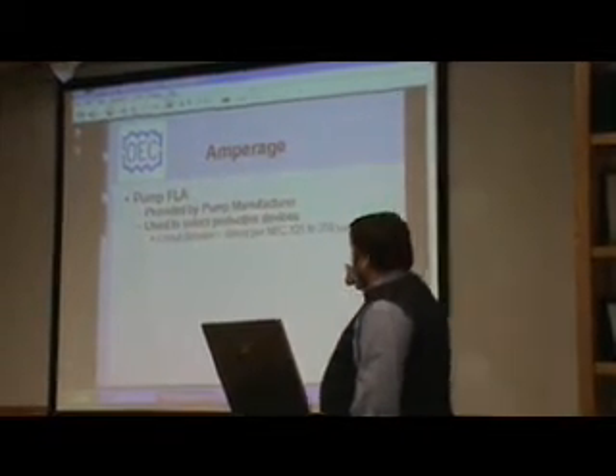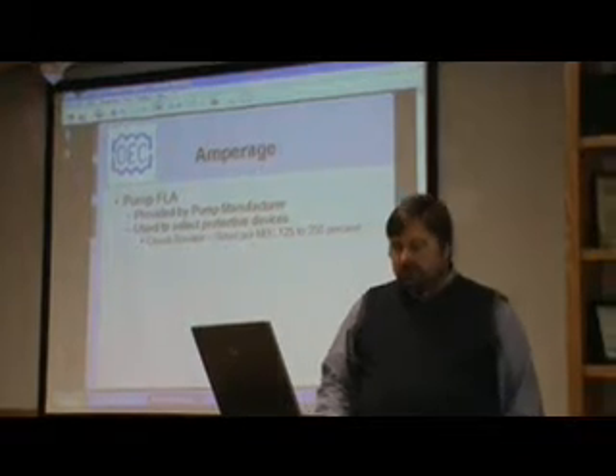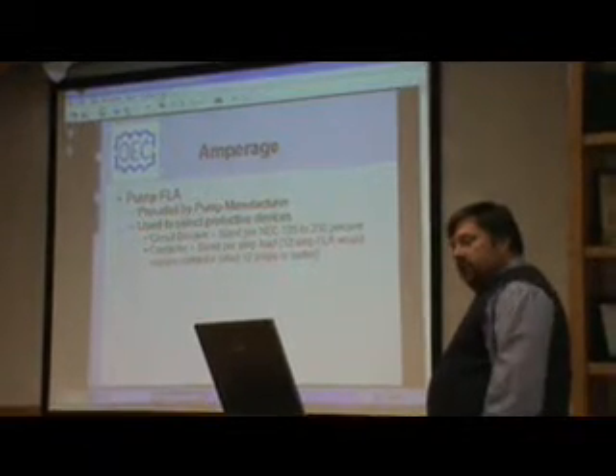But we have the ability, if you look here, per the National Electric Code, we could go 250%. So with a 10 amp load, we could actually put a 25 amp breaker on and still be within National Electric Code. The next thing we use that amperage for is to select the contactor that's used in the panel.